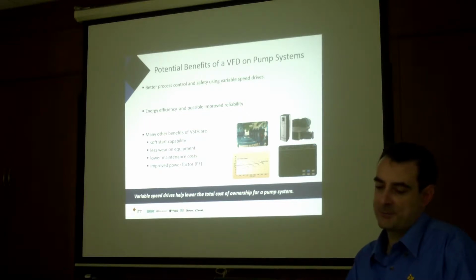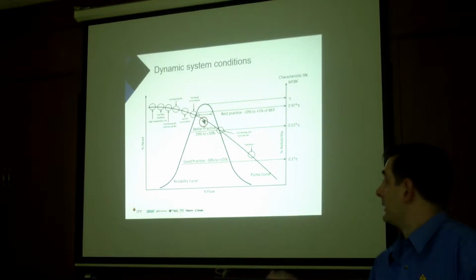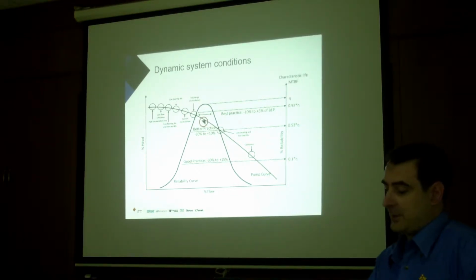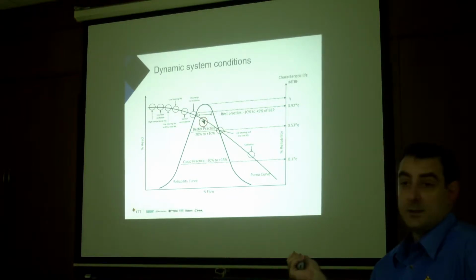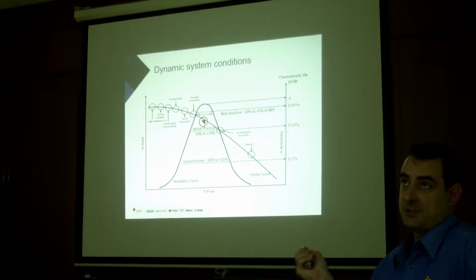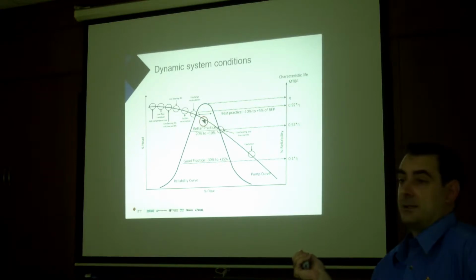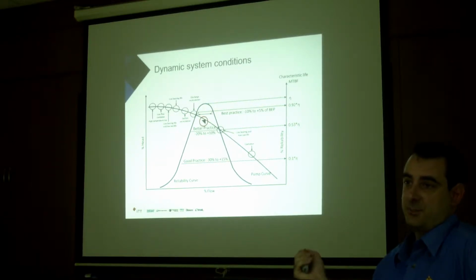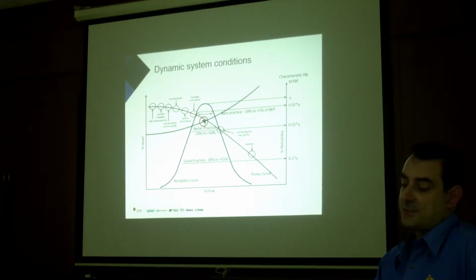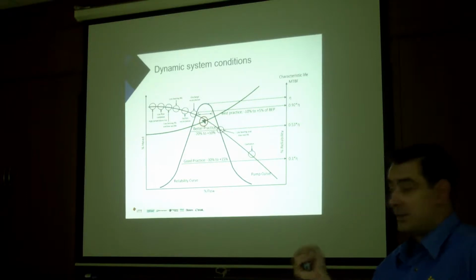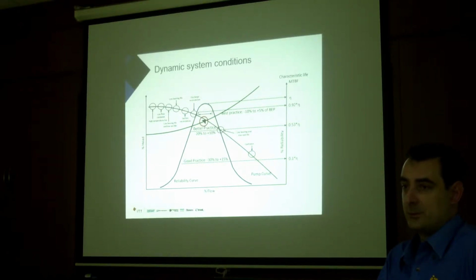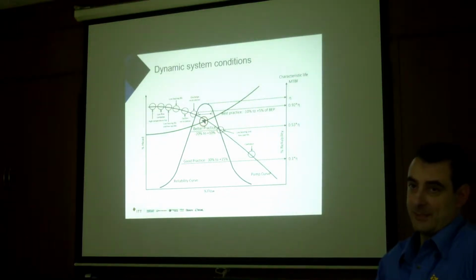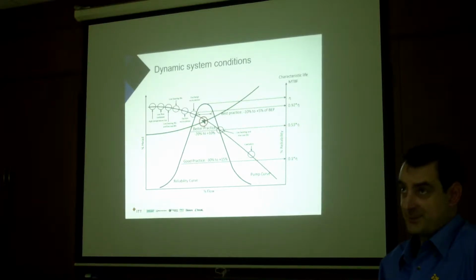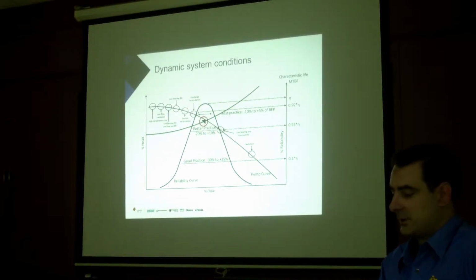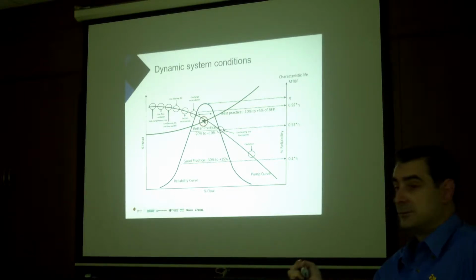So with the Pump Smart solution, we consider more where the pump is operating. A normal selection, rated duty, is going to be as close as possible to best efficiency point. But very rarely, especially in tank terminal applications, do they ever operate here, at full speed, best efficiency point. Usually, especially in the tank terminal, this condition is when the supply tank is very low, so it's the maximum amount of total dynamic head. Also maybe the most viscous product, so the friction loss is the highest. But most of the time, the tank terminal will operate down here, run out condition.